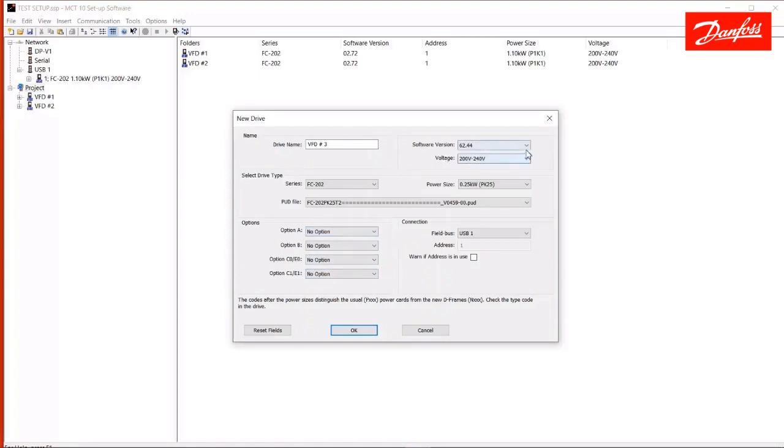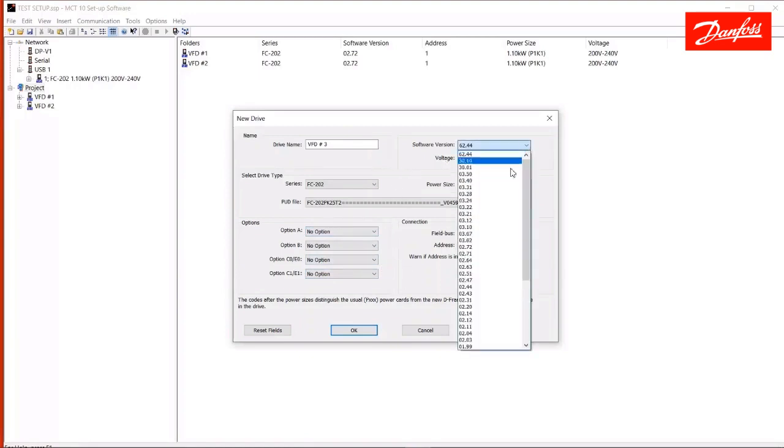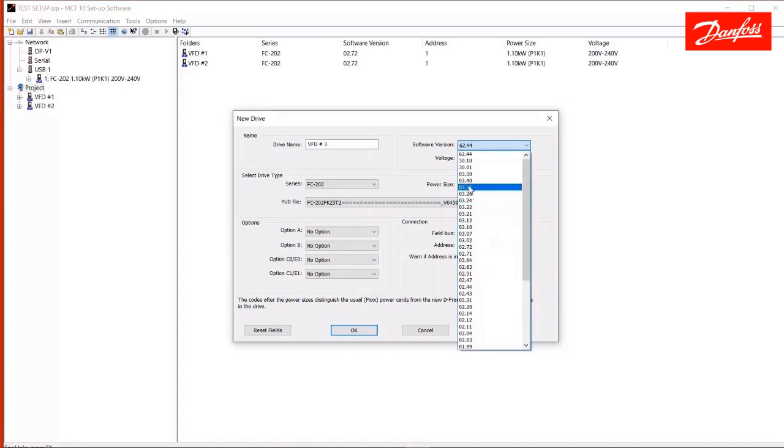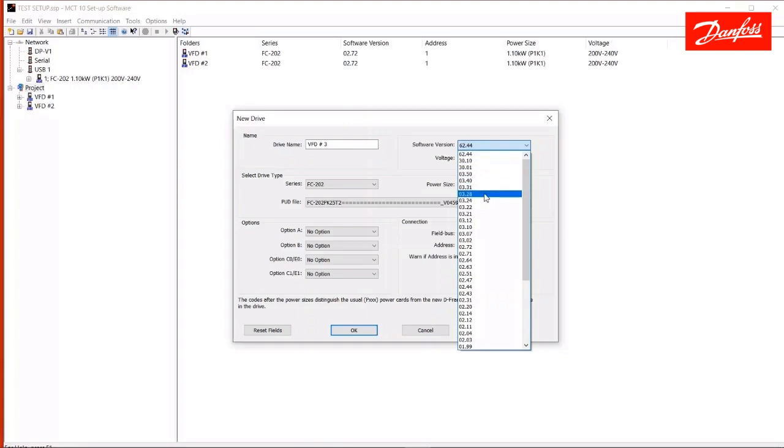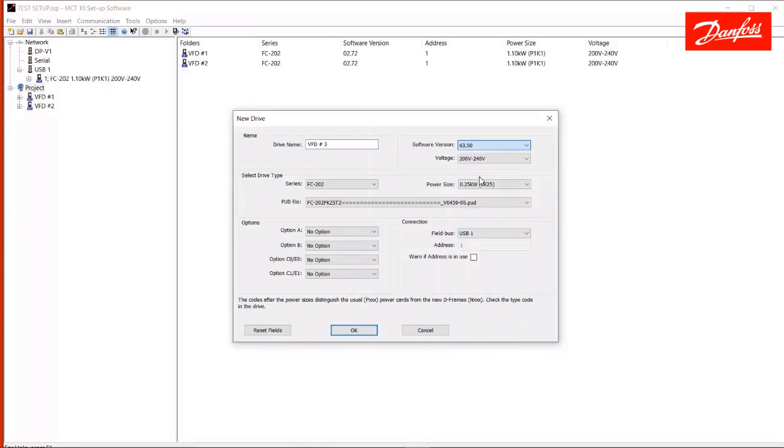Then we select the software version here. If you do not know the software version of the drive that you intend to later connect to, I suggest you choose the highest software version before we get to the double-digit numbers. Ignore those. Those are special versions. So, again, if I know the version of the drive that I wish to connect to later, I'll select it. If you don't, just select the newest version.